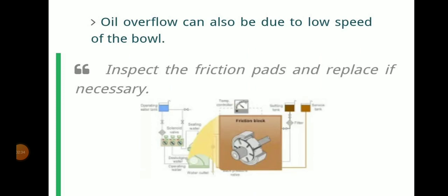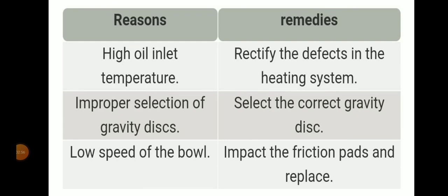Oil overflow can also be due to low speed of the bowl. Inspect the friction pads and replace if necessary. So the reasons are high oil inlet temperature, improper selection of gravity disc, and low speed of the bowl.